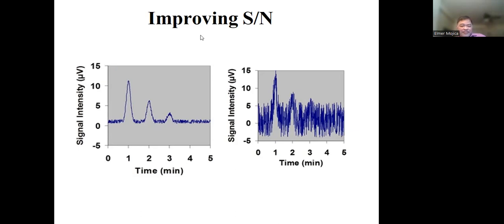Okay? And if you have a signal-to-noise ratio like that, this is the noise. You're good. But if your noise becomes 10 times compared to this one, it will affect your signal. Do you see that? So if you look at the signal-to-noise ratio here, maybe if I can assign values, this is around 52, this is around 26, and this is around 10.